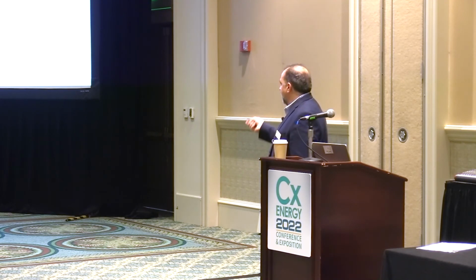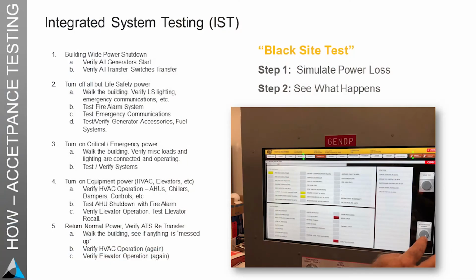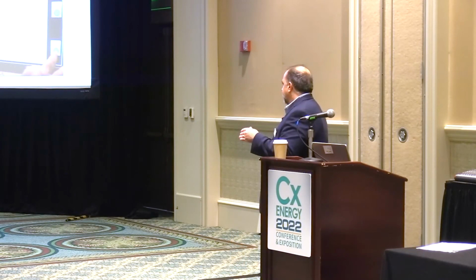Anyway, so once we do all those, generators tested, the transfer switches are tested, the fuel systems are tested, and I got checklists completed and everybody signed off, then we'll go through and do the full EPSS functional testing of the whole emergency power system, which seems a little redundant sometimes, but that's when we do, whether it's part of integrated systems testing or it's just a generator only test where we're going to turn off power to either the whole building or certain branches and watch everything happen automatically, right?